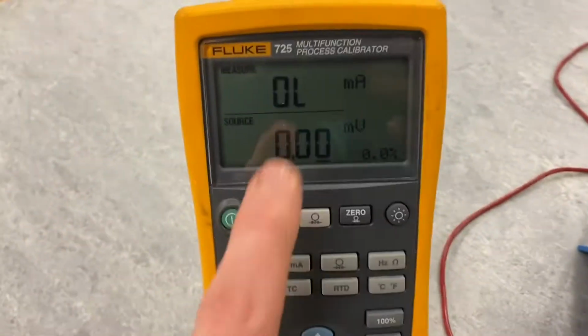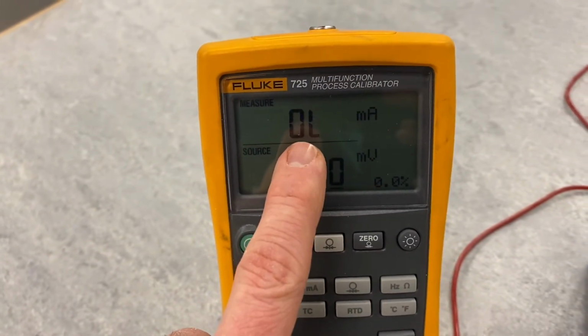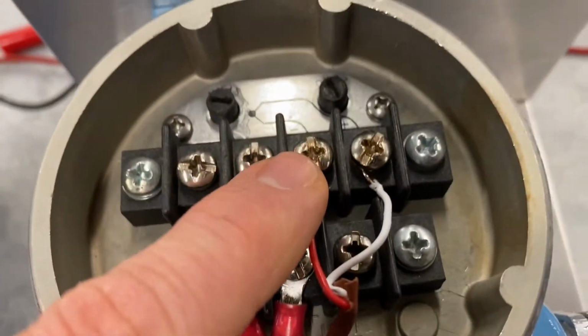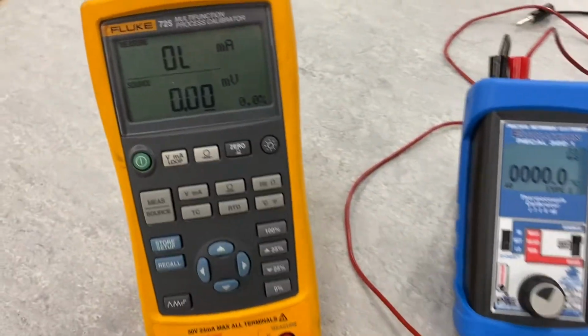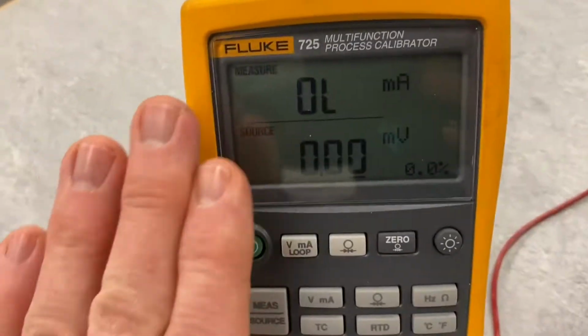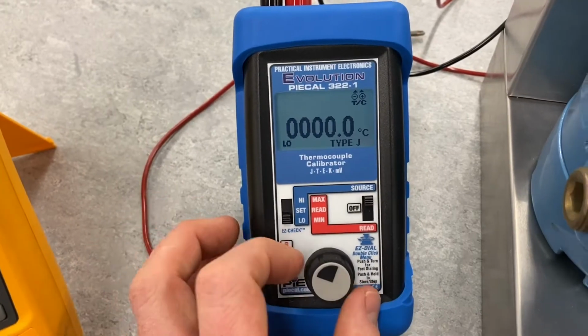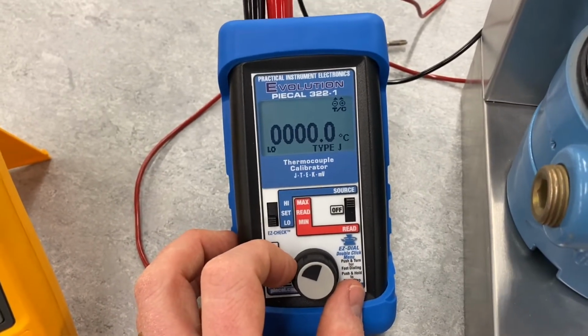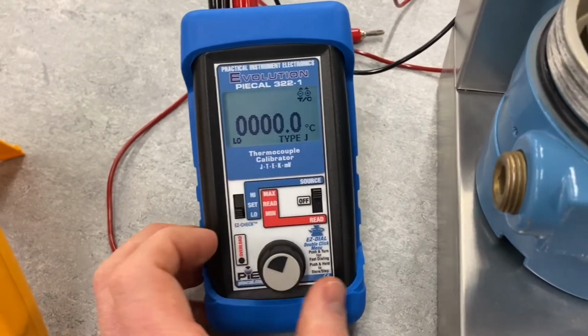We're going to be reading our milliamp value over here right now. It's overload right now. It's open loop because we have the thermocouple disconnected. So we're still using this to read the milliamp value, but now we're using this to source our millivoltage of the thermocouple. So right now it's set for 0.